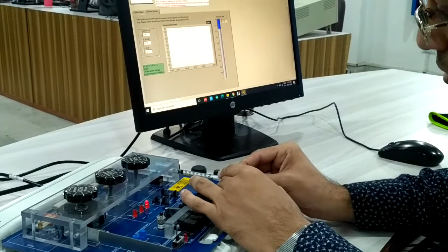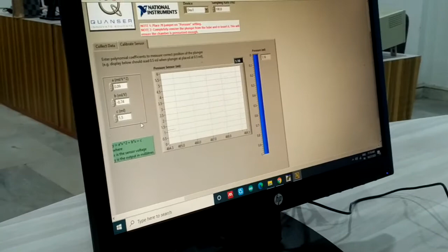At 0.2, what is it showing? It is showing a large amount of error there. As we move towards the zero end, we face a lot of back pressure, a lot of reading variation. But as soon as we move back to 0.6 and 0.8, it works perfectly fine. So it's better to take readings at 0.8, 0.6, and 0.4. If at these 3 points the readings at the sensor, the scale, and the syringe are coming out the same, then that is the appropriate value for this c.